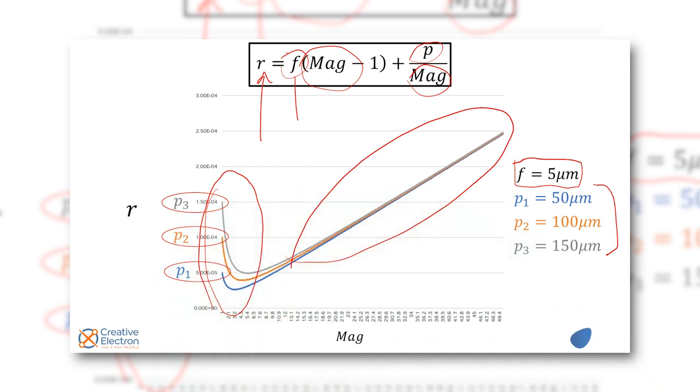So magnification shows up in the denominator and the numerator, so it's a straight line and an inverse function and that's exactly what we see here. Depending where you're going to be, you have to pick specific features of the x-ray imaging system to optimize a specific application. There's no one answer fits all.